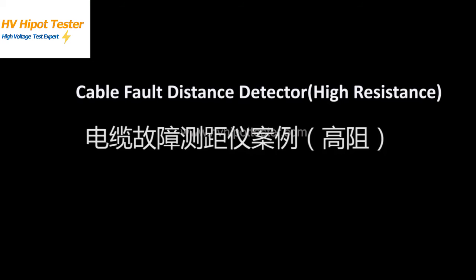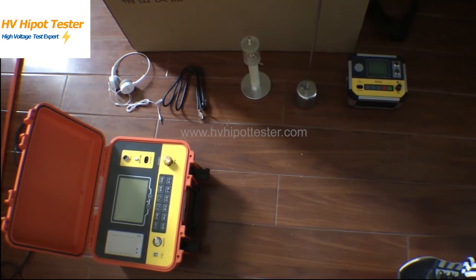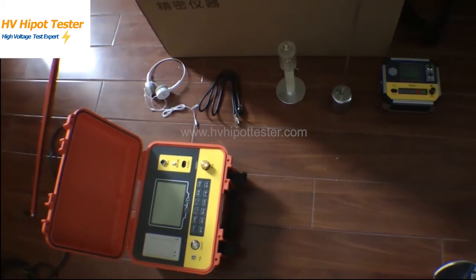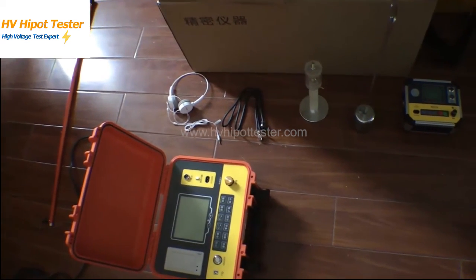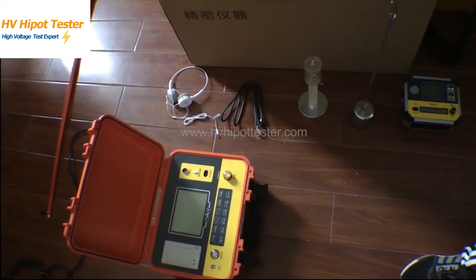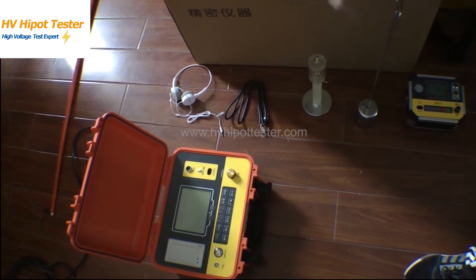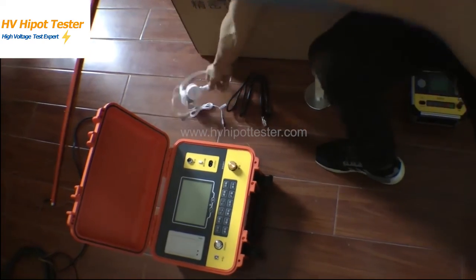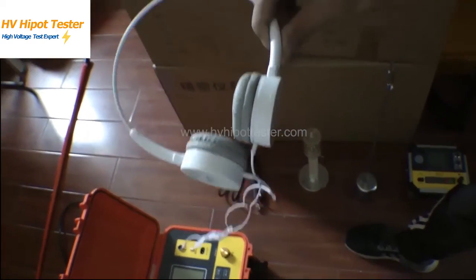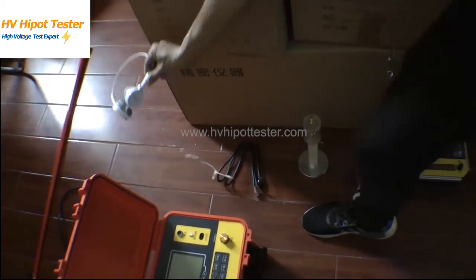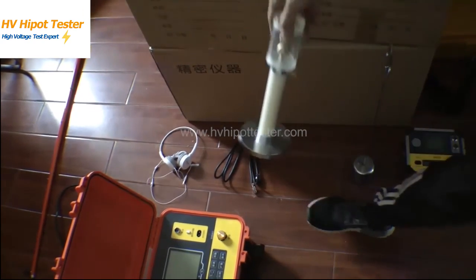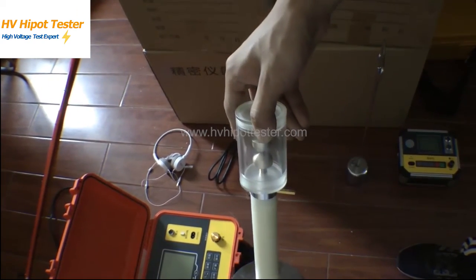Cable fault distance tester high resistance case. When testing high resistance fault, we are using the flashover method. Now let's introduce the accessories and instruments we need.